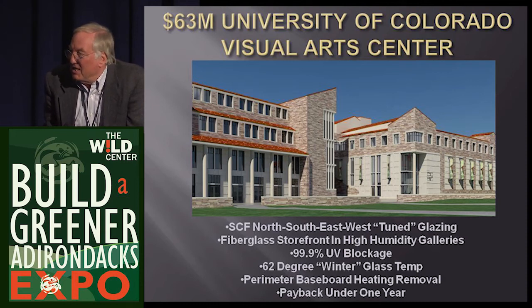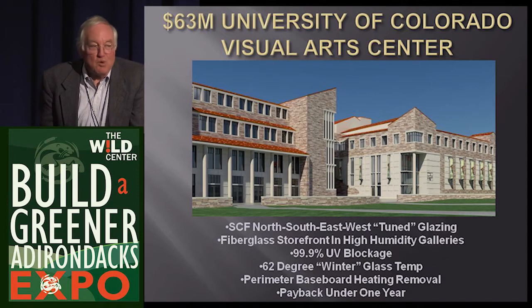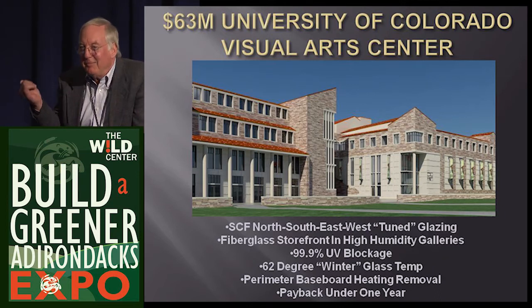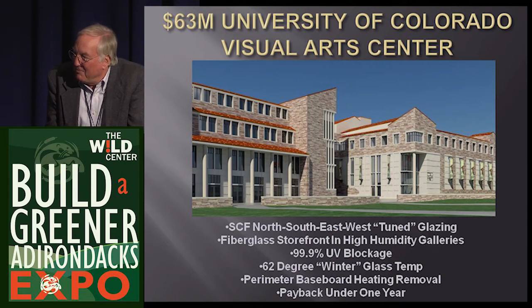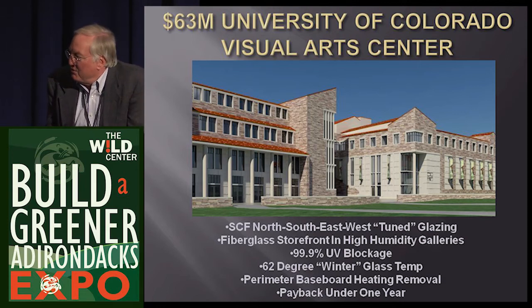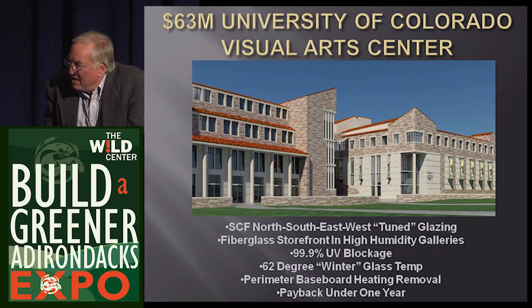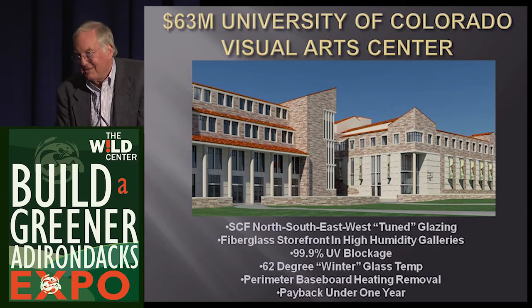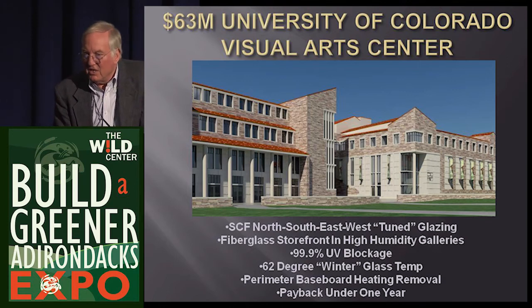Whether you want high heat gain through south windows depends entirely on architecture - good passive solar design with overhangs in summer, seasonal foliage, and movable insulation enables high SHGC glass on the south. We also pulled all perimeter baseboard heating. The holy grail in commercial glass payback is changing the HVAC system to remove those bulky radiators. Going to super-insulating glass with film and krypton cost the project $263,000 extra but saved $242,000 by eliminating perimeter baseboard heating.